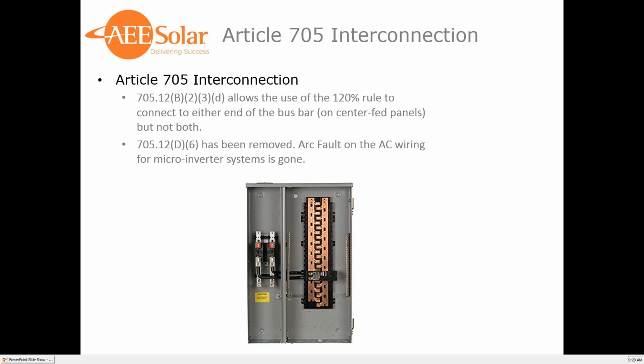So another change is 705.12 D6 has been removed. It's arc fault on AC wiring for microinverter systems, and it's gone. There really were no arc fault breakers that would work for those circuits, so they ended up just removing it from the code article.